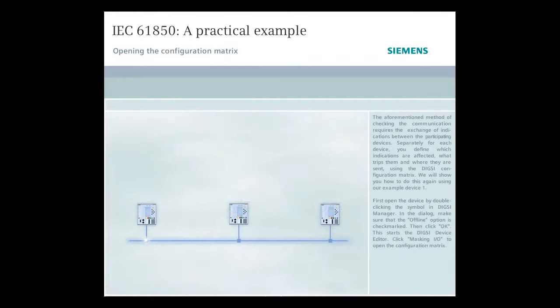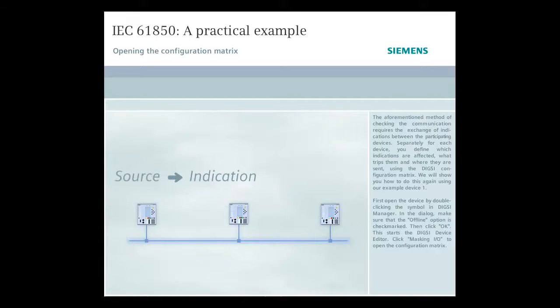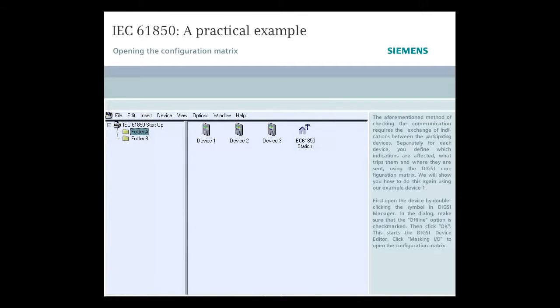The aforementioned method of checking the communication requires the exchange of indications between the participating devices. Separately, for each device, you define which indications are affected, what trips them, and where they are sent, using the DIGSI configuration matrix. We will show you how to do this again using our example, Device 1.